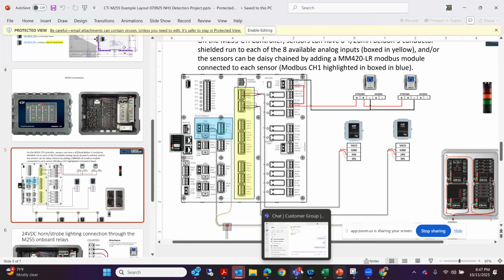Yeah, that's perfect. So we're seeing the backup generators as well. Initially, I wasn't a big fan of standalone ammonia detection controllers because it was easier to go to the PLC. But because of wanting to keep the detection live for so much longer, that doesn't make sense anymore, because the PLCs have racks all over the place. Now you have to battery backup every one of them, and they may not be on the same circuit. That makes it a much more challenging project, whereas with a standalone system you can bring in one dedicated circuit or run off a genset, and your ammonia detection is still active and can still fire the relays necessary to protect the employees.